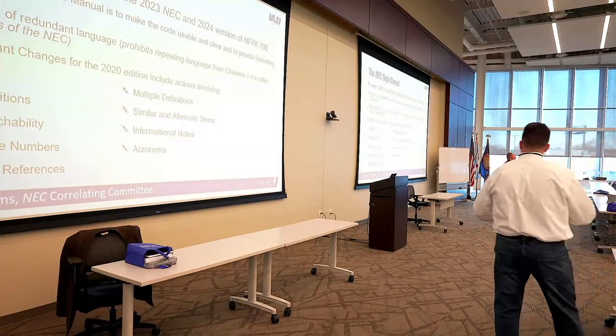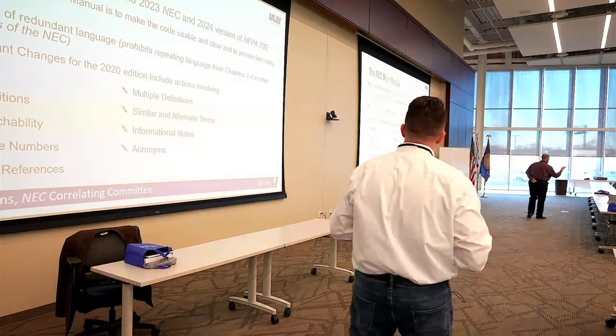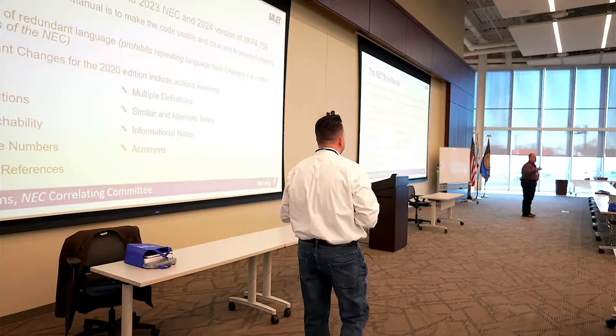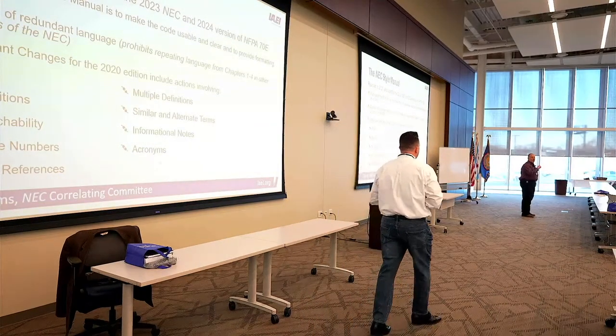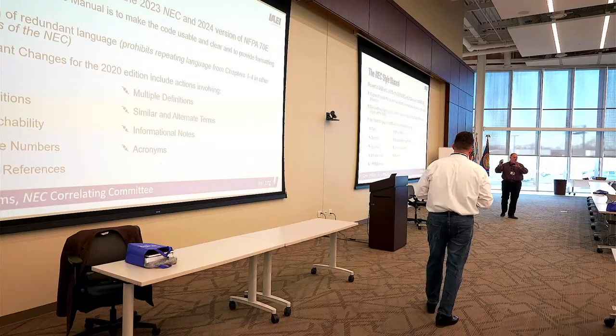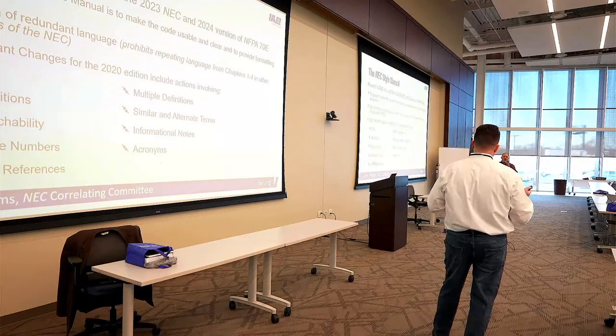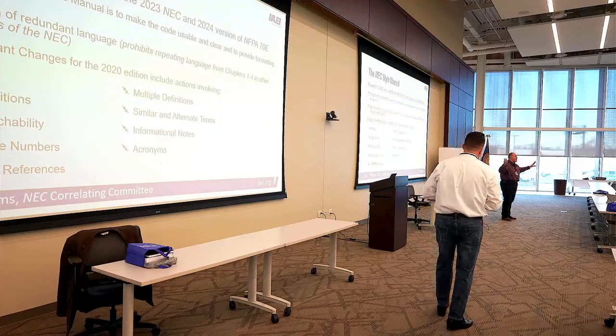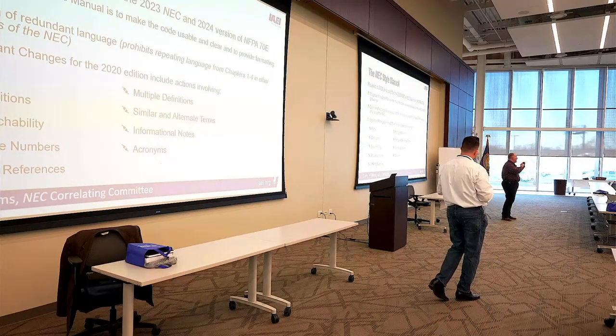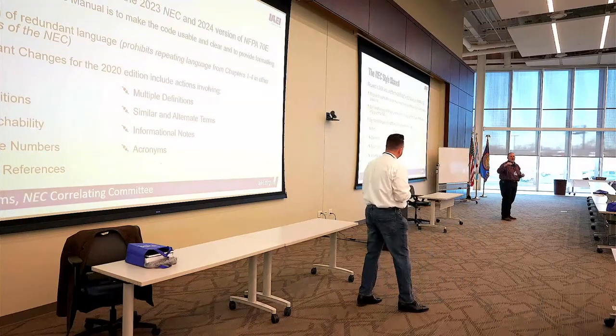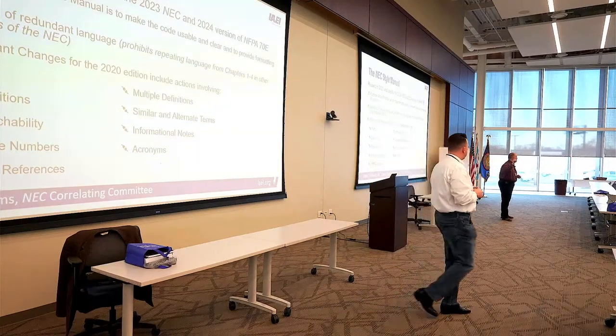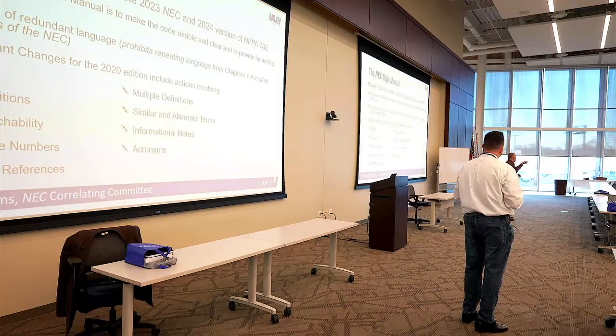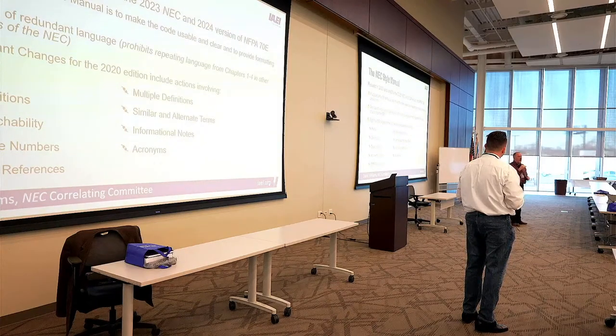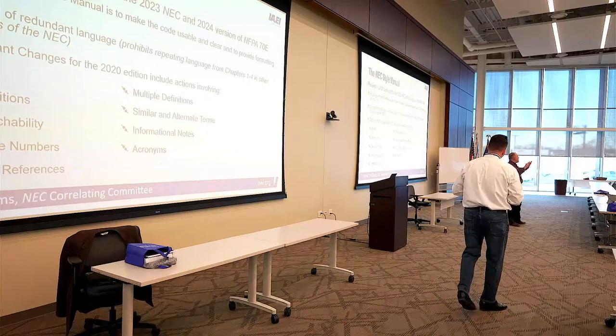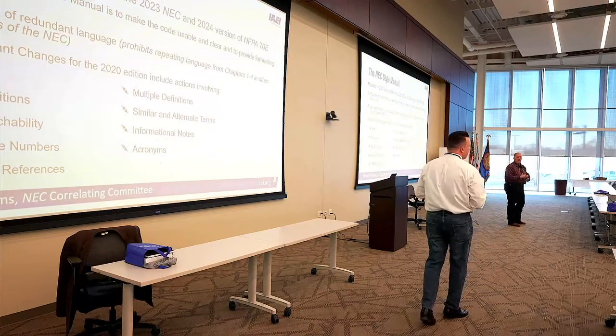One of the changes - when they change the style manual, that tells you, for example, one of the changes we're going to talk about is moving the definitions. All defined terms now have to be in Article 100. That's in accordance with the style manual. For the 2023 code cycle, the .2 sections in all of the articles are pretty much driven to be reconditioned equipment requirements - not necessarily driven by the style manual for that cycle, but they added requirements for the 2026 cycle saying all your .2s will be listing requirements, and all your .3s will be reconditioning requirements. So they drive the organization of the book through the style manual.